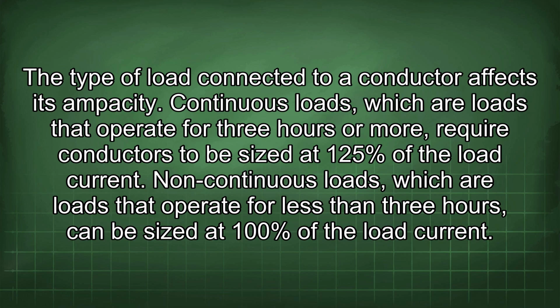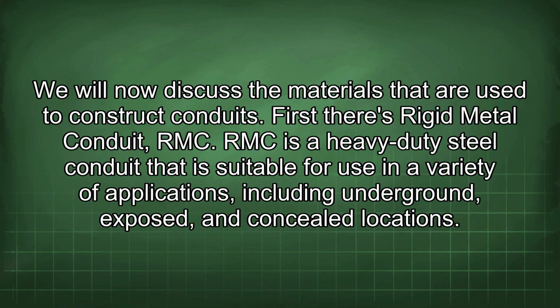Continuous loads, which are loads that operate for 3 hours or more, require conductors to be sized at 125% of the load current. Non-continuous loads, which are loads that operate for less than 3 hours, can be sized at 100% of the load current. We will now discuss the materials that are used to construct conduits.